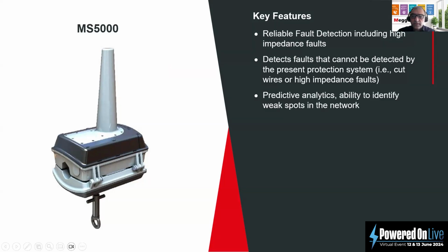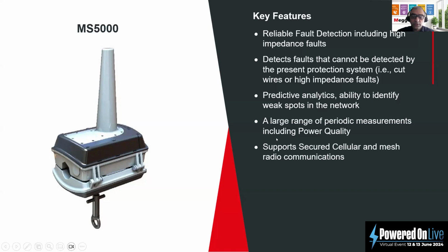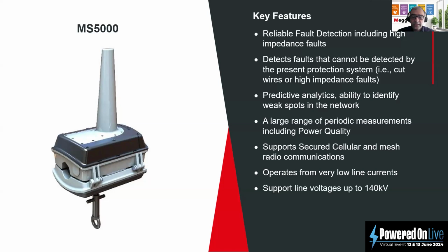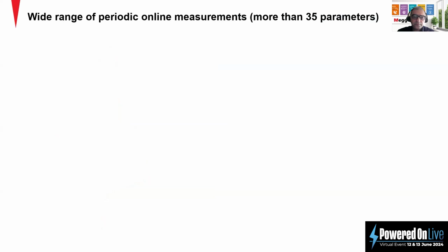There is predictive analysis of the network, with the ability to identify weak spots, and a large range of periodic measurements, including power quality parameters. They support secure cellular and mesh radio communication, and operate from very low line current, as low as 1.5 amps, supporting line voltage up to 140 kV, and can be integrated with the utilities' control room software.